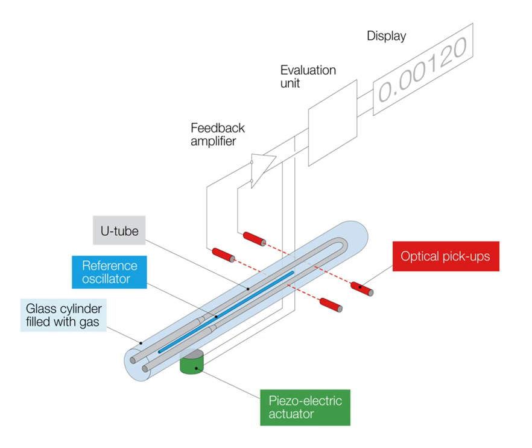Overfilling the oscillator beyond the bearing points is irrelevant to the measurement. For this reason the oscillator can also be employed to measure the density of sample media that flow through the tube. In modern digital density meters, piezo elements are used to excite the U-tube, whereby optical pickups determine the period of oscillation. This period tau can be measured with high resolution and stands in simple relation to the density rho of the sample in the oscillator: rho equals a times tau squared minus b.